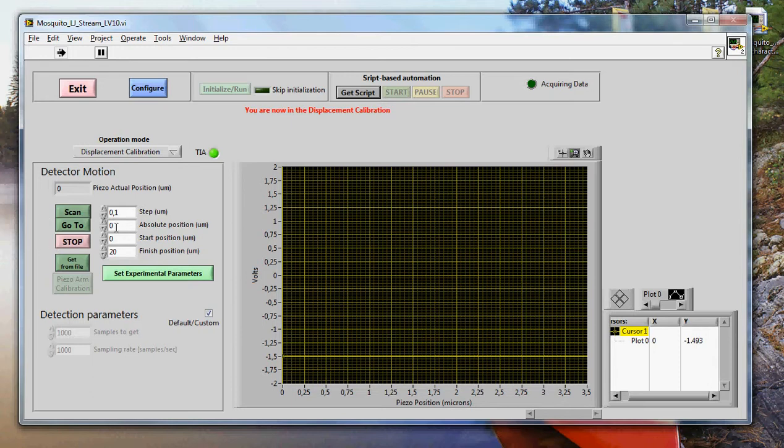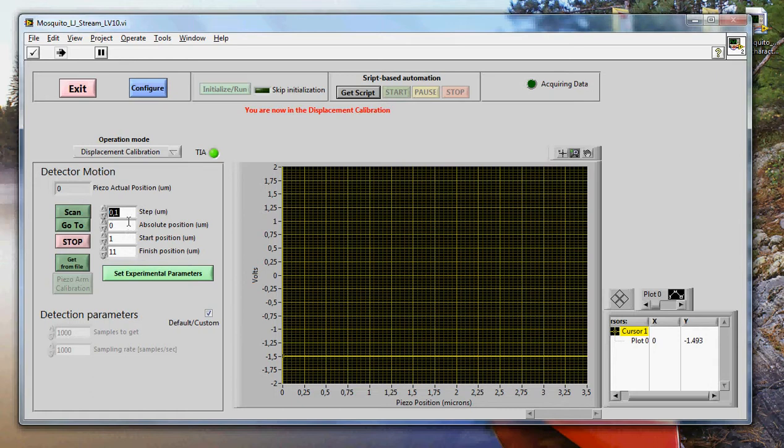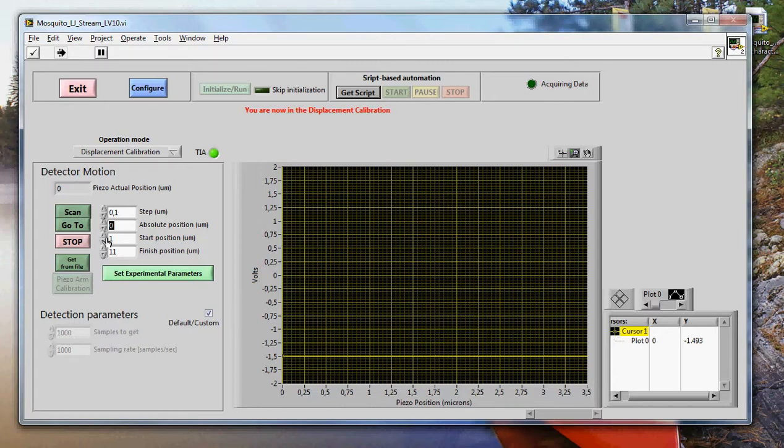Here you have, again, the piezo controls, and the way you do this operation here, you have the piezo in contact with the tip of the transducer, and you push the transducer with the piezo from one position, initial position, let's say 1, to a final position. Let's make it 11, with a certain length of a step. Once you put these parameters in place, you can actually put your piezo in an absolute position here, and hit the scan button. If you wait long enough, step by step, the piezo will reach the final position, the scan will end, and it will ask you to save the data.